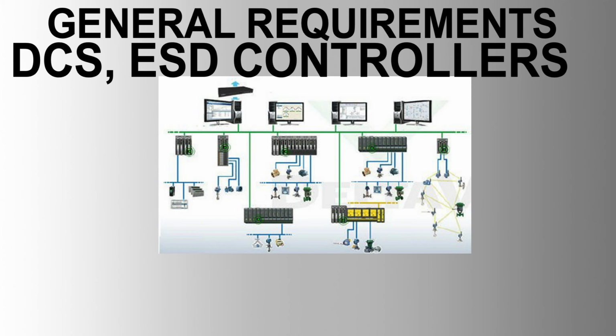Digital outputs provide volt-free contacts capable of withstanding 24 volt DC minimum. Contacts are software selectable SPST-NO or SPST-NC and rated for 2A at 30 volt DC. Replaceable load fusing is provided on an individual channel basis.